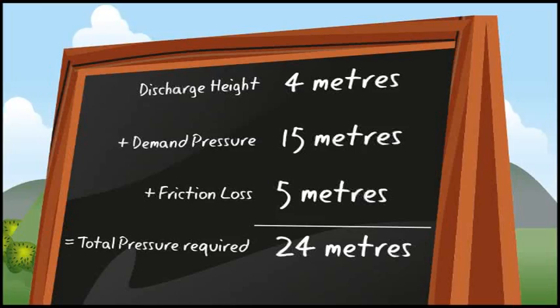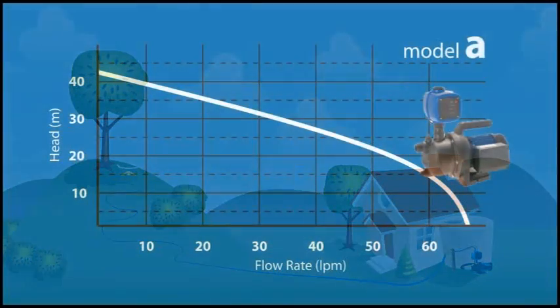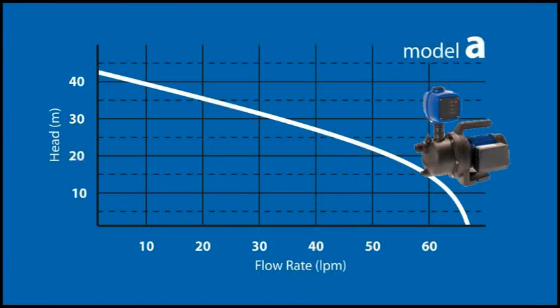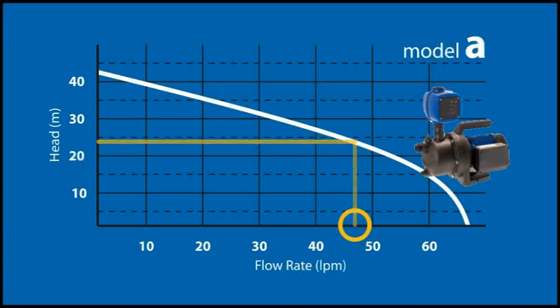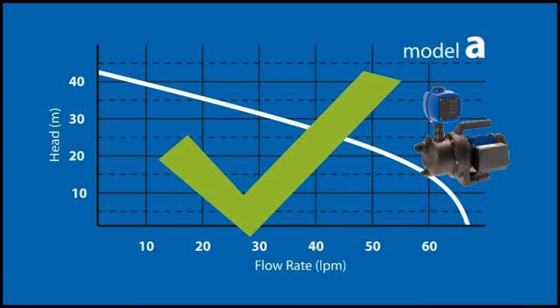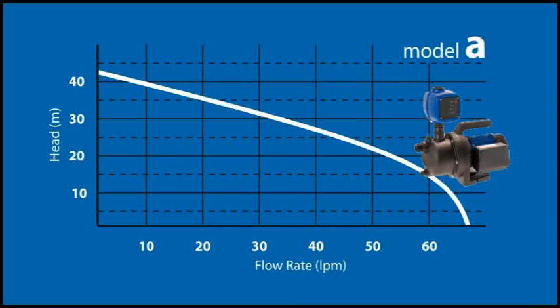Let's go back to the pump curve for model A to see if changing the diameter of the pipe will make this model a viable option once more. This time, we need to find 24 metres on the head or vertical axis and run an imaginary line across the graph till you hit the pump curve. Draw a straight line from this point down to the horizontal axis. By increasing the diameter size of the pipe, model A can now produce both the pressure and flow rate to meet Aunty Flo's needs.